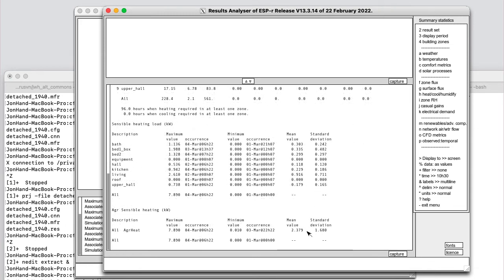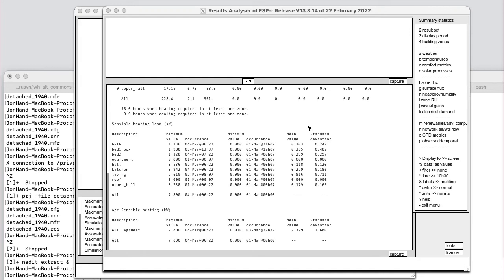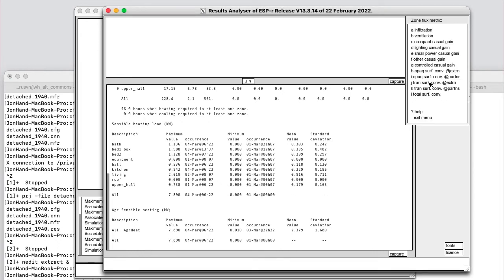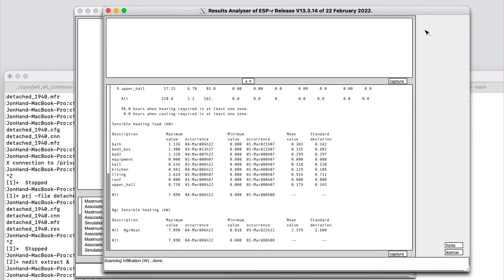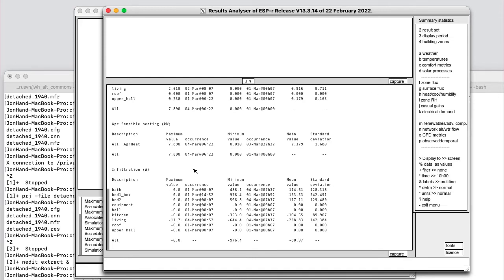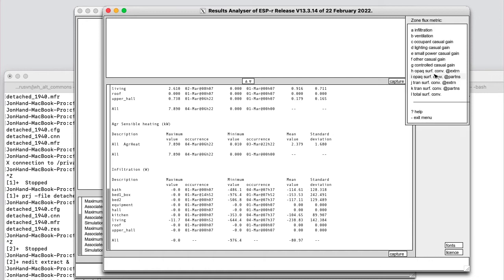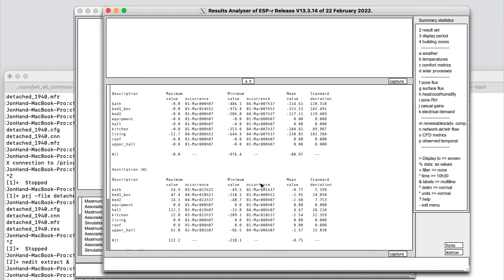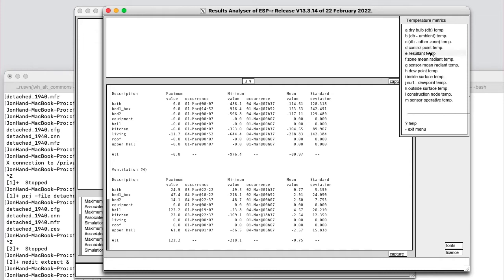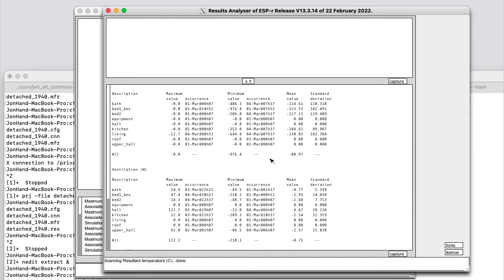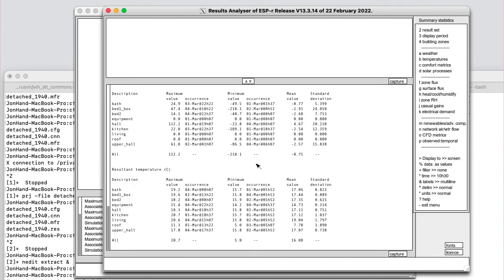Looking through these various topics, I would then build up an idea about what things would be useful to include in an automation. For example, let's go and look at one of the classic things that drives the need for heating is infiltration. And so now I have watts in each of the room over the month, and I'm getting when was the maximum and the minimum of where infiltration was an issue. Ventilation is the impact of airflow between rooms. Again, these are relatively small numbers at the moment.